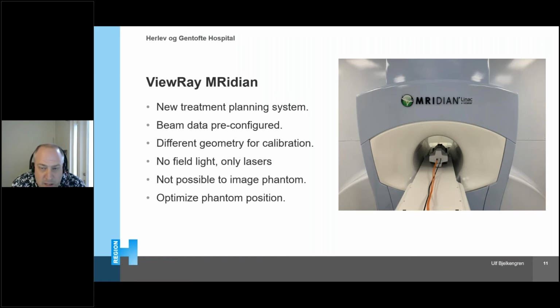You have to rely on the lasers because you don't have any field light. On the TrueBeam and on the Halcyon, at least you can take images of the Delta 4 Phantom to help in alignment if you'd like. You can't do that on a MR Linac. I guess the electronics of the Phantom wouldn't like the gradients and you wouldn't get any signal either. But one function in the software that is really useful for MR Linac is the optimize phantom position. And also this is not only the optimized phantom position, but also the Delta 4 software.